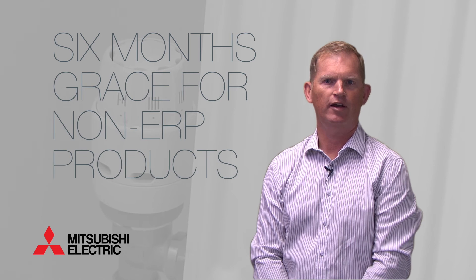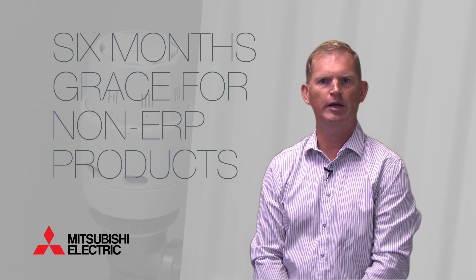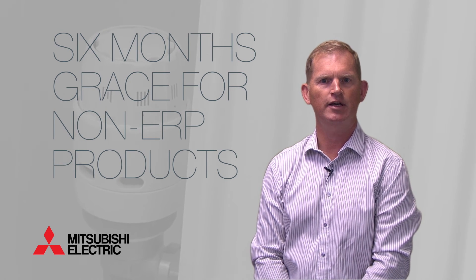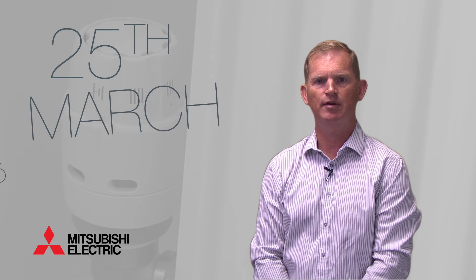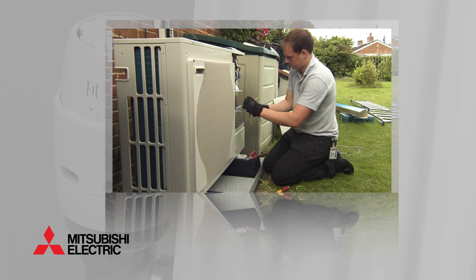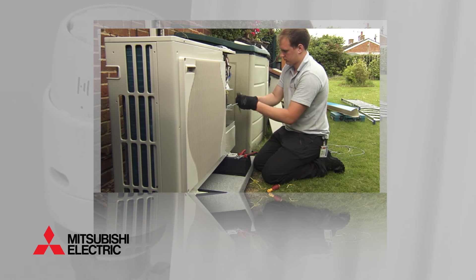The updates to the RHI regulations also come into force on the 26th of September. It's important to note that installers will still be able to fit heating products which enter the market prior to this date, using either the new or old MCS installation standard for the RHI. However, this period ends on the 25th of March 2016, after which all MCS certified heat pumps must be installed using the latest RHI standards, which are in line with ERP.